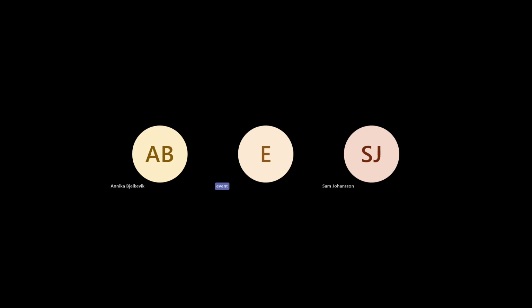So it's a very accurate capacitive distance measurement on the silicon components that are on a cantilever. And as the tilt meter moves, you have very small distance changes that are measured with a capacitive principle. So it's actually surprising how accurate it can be for a little silicon chip, which is about 1 millimeter by 1 millimeter. So the typical specs, I mentioned them before: in-place inclinometers and tilt meters can have a repeatability of 0.002 degrees.